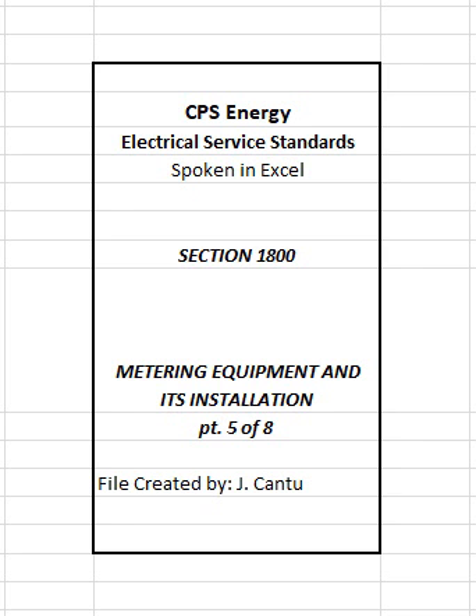Meters may only be grouped using one of the following methods. 1. Modular metering equipment. 2. Auxiliary busbar gutter. 3. Auxiliary wire gutter. 1808.1 Grouping meters with modular metering equipment. Modular metering equipment will be allowed where the general installation requirements and specifications outlined in this section have been met and approved by CPS Energy. Refer to Figure 1814.